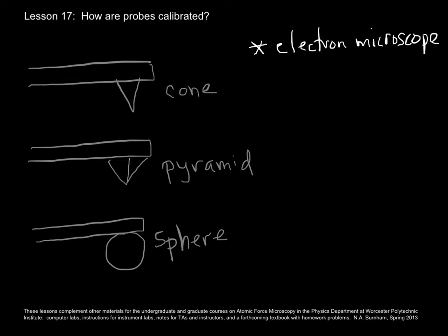Unfortunately, that means that you would have to have access to an electron microscope, and you have to be good at handling the cantilever chips such that they don't end up at the bottom of that machine. So you would like to have a tip calibration function that you can do within the AFM. So one of the early ideas was plastic indentation, meaning that you take a soft, malleable sample, such as indium, and you purposefully push hard your tip into it, and then you come back and with a low force, you image the hole that you've left.